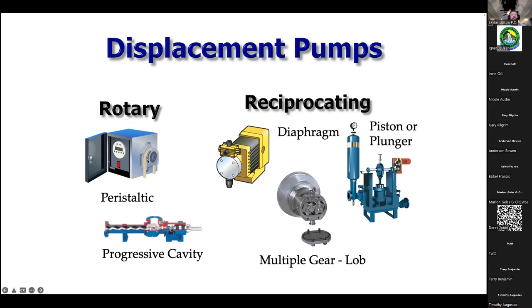From an examination standpoint, we consider where this pump is in its performance capacity — specifically the stroke-to-speed relationship. Ideally, we like to see the speed at 50 percent. That means the stroke is set so that during most regular flows, speed is at half — giving you maximum ability to adjust the pump down to slow injection rate or speed it up. This gives the most range of adjustment.